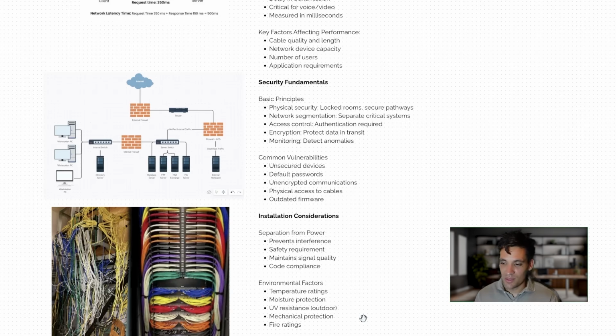We also need to be aware of things like temperature ratings, moisture protection, UV resistance if stuff's installed outdoors, mechanical protection, and fire ratings. One of the biggest installation considerations I see is just how messy communications cabling is. You look at a picture like this, a lot of installations end up looking like that because often you're just running so much cabling, so many different connections, and it becomes a mess to fault find and debug.